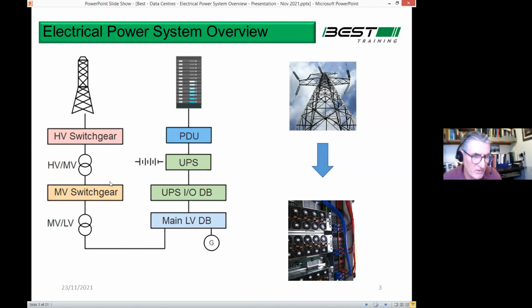It's really from here down, from the MV switchgear downwards, that the electrical engineer on the data center gets involved in. So the first thing is the MV switchgear, or medium voltage switchgear. Medium voltage is above 1000 volts up to 35,000 volts. So in Ireland, it covers our 10 kV system and our 20 kV system. And it's either one of those two voltages you'd be distributing around the site.